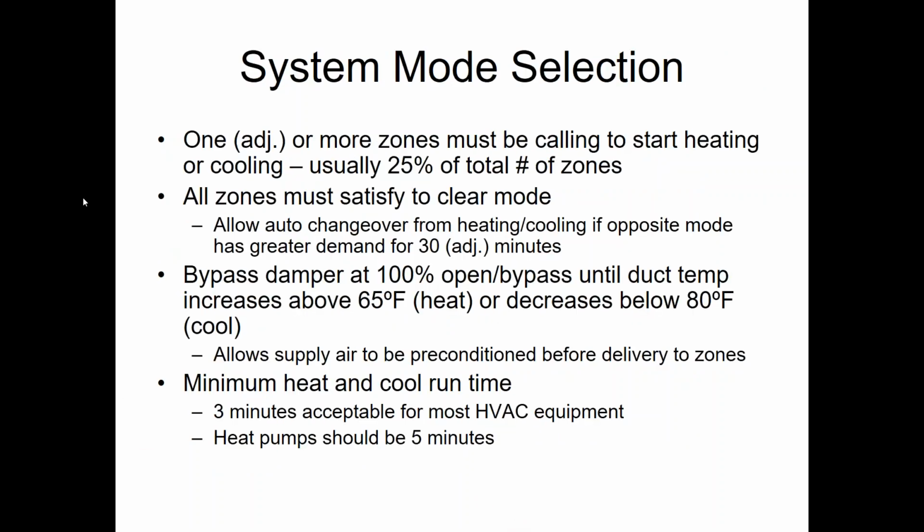It's not very difficult to do. Actually, all constant volume control systems will do that. Even ones for your house, if you get a Honeywell zoning panel, they'll ship it to you with a leaving air temperature sensor for your house for that exact reason. The only one that doesn't do it is an Infinity residential control system. It does it a different way, but that's a whole other webinar.